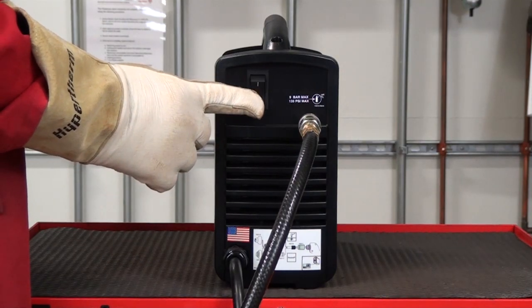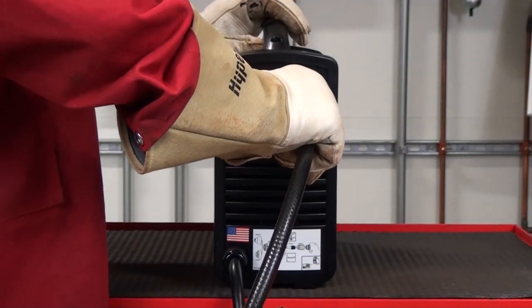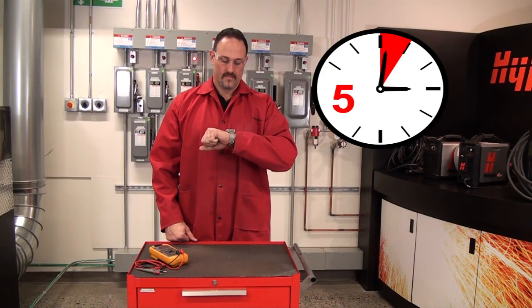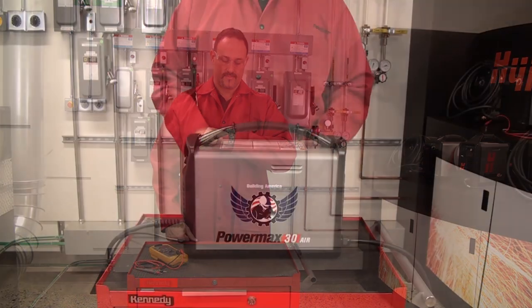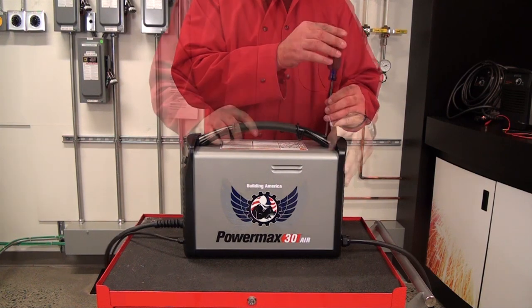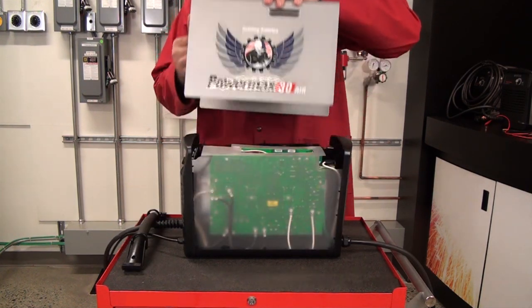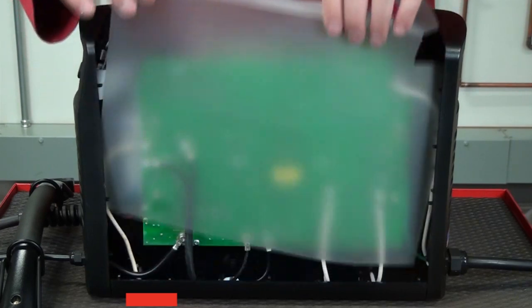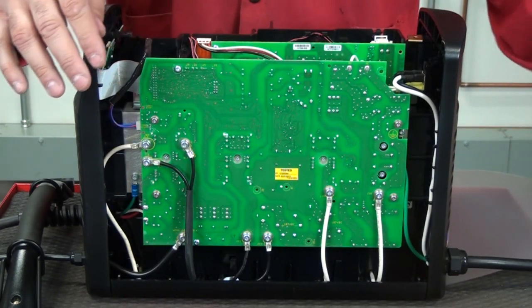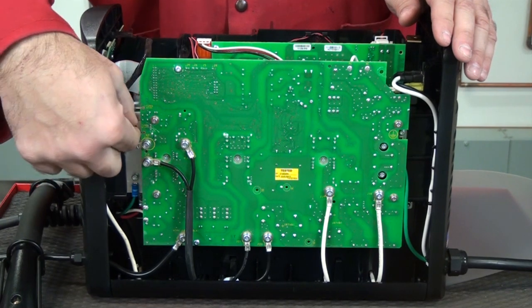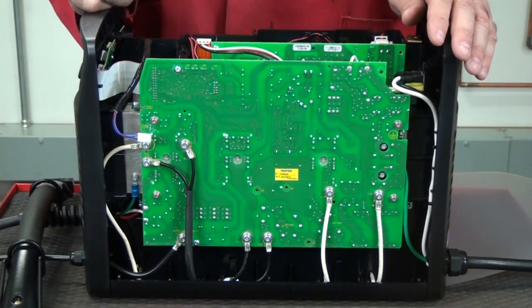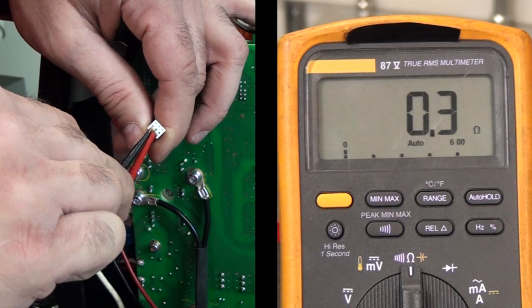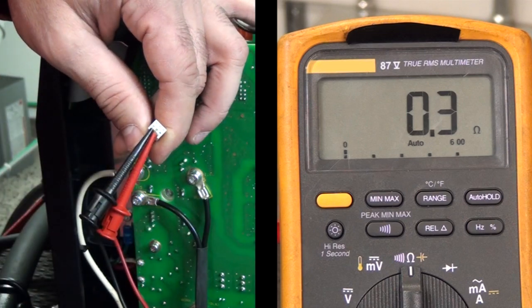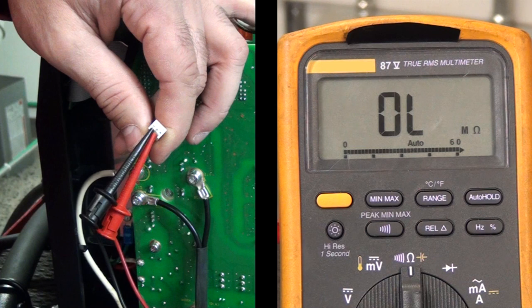Make sure all power and gas are completely disconnected, and you have waited 5 minutes for remaining power to bleed out of the system. Remove the power supply handle and cover, and then also the component barrier. Disconnect the cap sensor connector at J12 on the heatsink side of the power board by pushing the tab on the connector toward the plug and pulling the plug out. Measure the resistance from the orange wire to the blue wire. It should measure less than 1 ohm. If it measures high resistance, the cap sensor switch circuit is open.